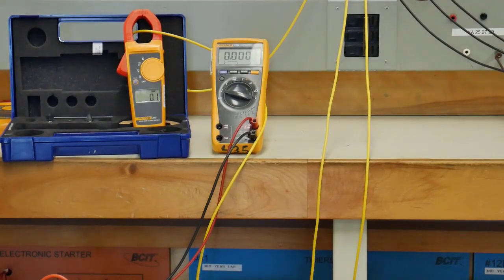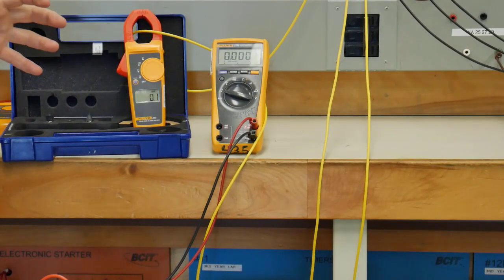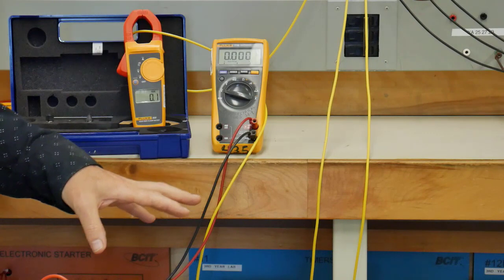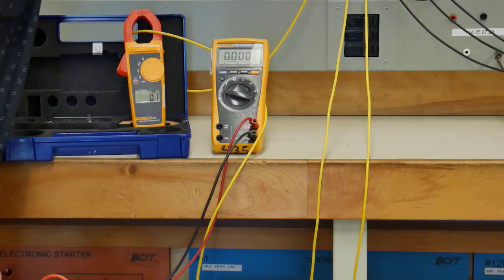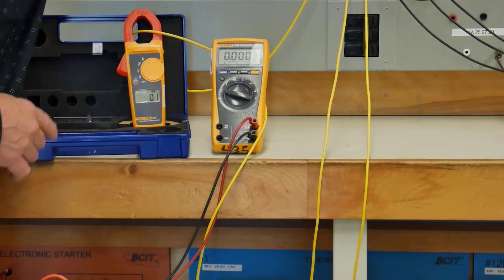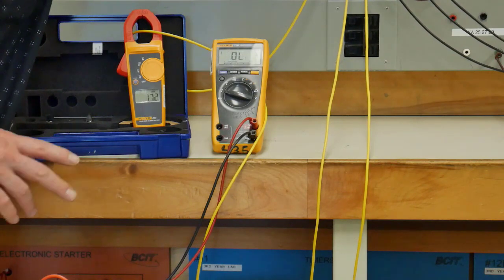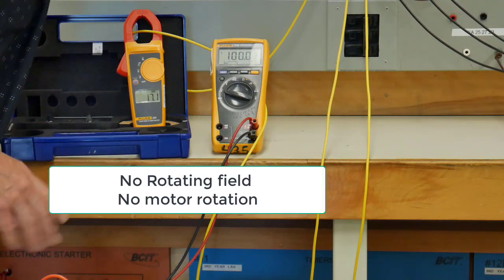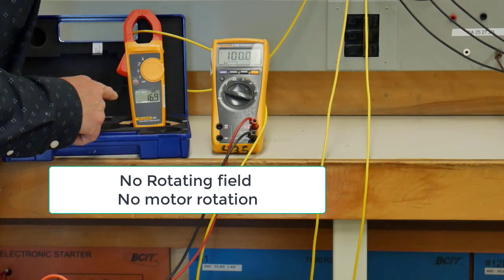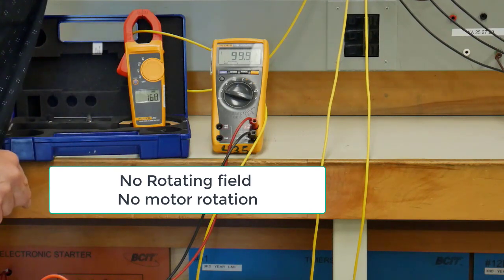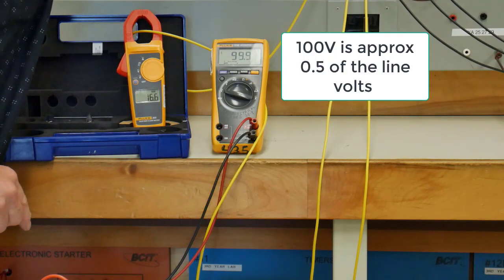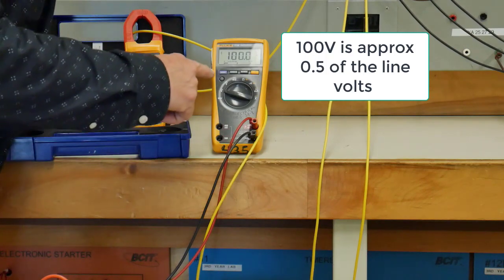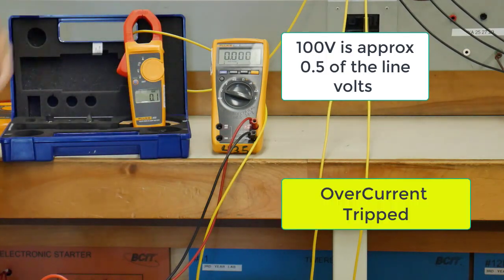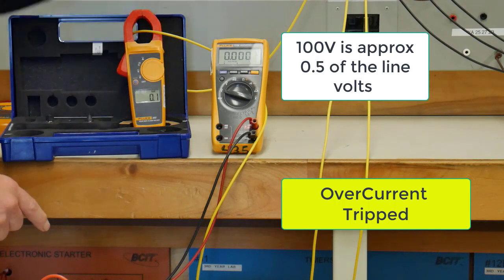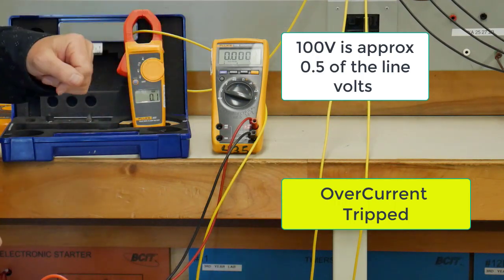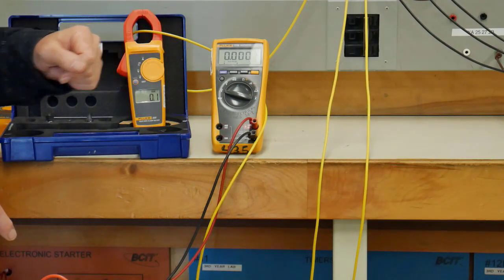Okay guys, we're going to leave it single phasing, no load, and we're going to try and start it up. Here we go. Now let's see what the current does. The motor's not turning at all. It's just sitting here humming. We're up to 17 amps. Phase voltage here: the voltage went down to about 100 volts.